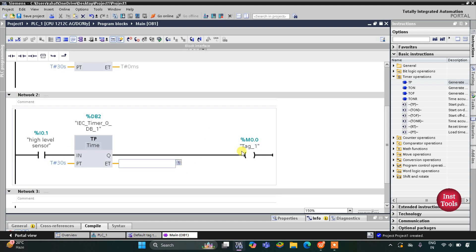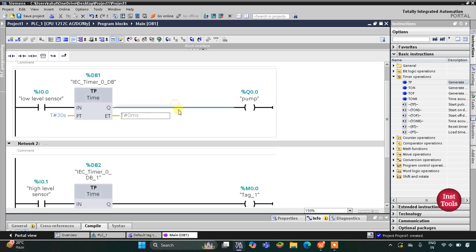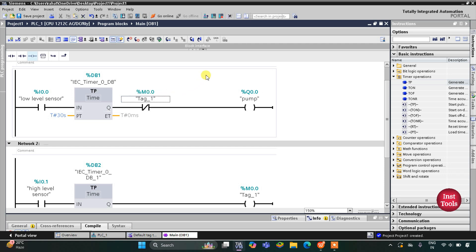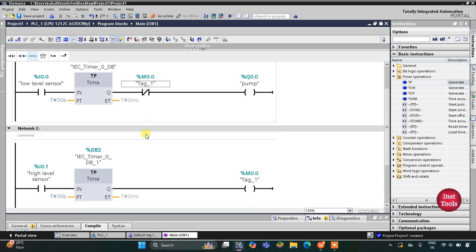After that, M0.0 will be used here as a normally closed contact, with address M0.0. We have now completed the ladder diagram. When the low level sensor detects the level is low, the pump will turn on for 30 seconds. If the high level sensor detects the level is high, then M0.0 gets energized, and when it gets energized, this pump will turn off. When low level is sensed again, the pump will turn on again — and in this way it will continue cycling. I will start the simulation now.